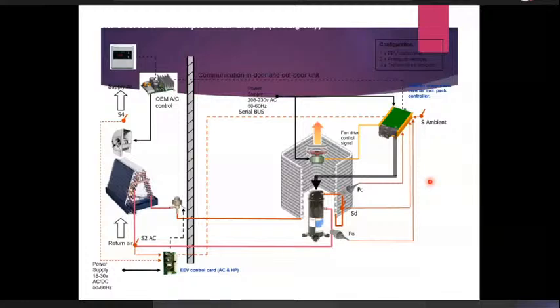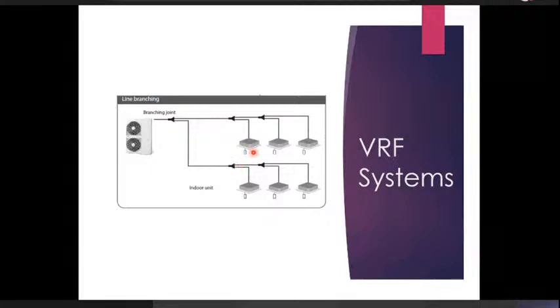Now, line branching becomes another important part of multi-indoor systems, VRF systems. VRF stands for variable refrigerant flow systems. Typically in a commercial application, in an office, you have several of these cassette units with a corded remote. All of these are evaporators where we are taking heat from the occupied space, and then the refrigerant is being merged. As you can see, there's a particular type of connector here, then another connector here, and all of this goes into the condensing unit. So all the refrigerant is going there. There has to be a way to estimate the pressure drops and ensure that flow occurs through all of these branches in the desired fashion. And mind you, you will always be feeding as well as taking refrigerant back.